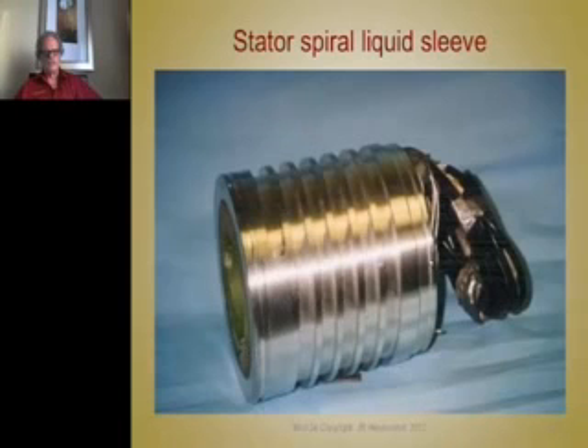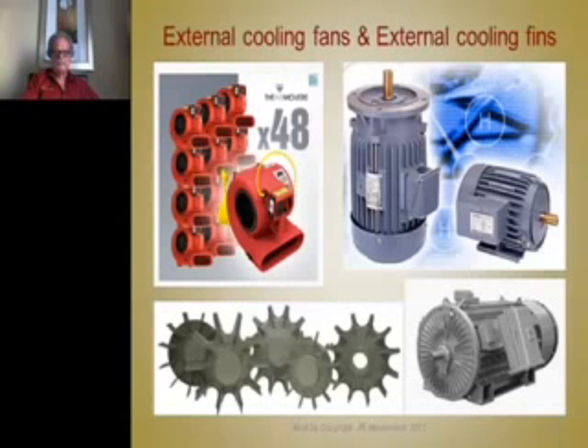And this, of course, has an O-ring seal at each end, and this slips in another tube where the liquid ethylene glycol enters. Sometimes, like on machine tool spindles, the ethylene glycol is refrigerated. They keep it at 70 degrees Fahrenheit. If they made it any colder, they could increase the power density and extract a lot of heat. But the problem is, if they make it colder, then the cold is going to take condensate out of the humidity of the air, and it's going to cause rust on the machine tool and things like that. So they try to keep the cooling media at room temperature.